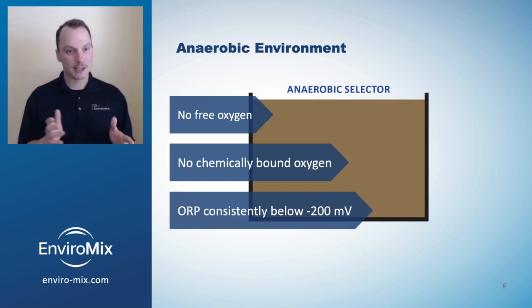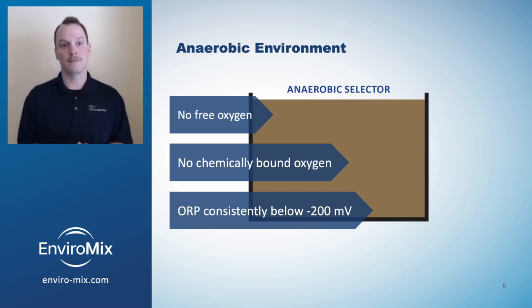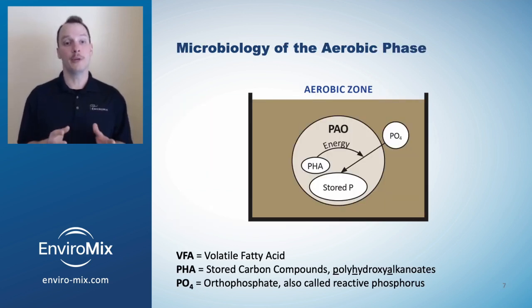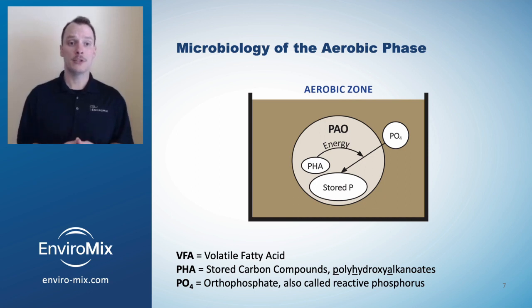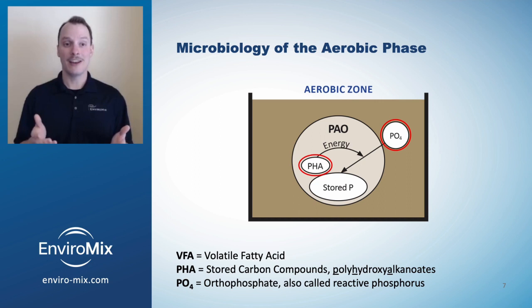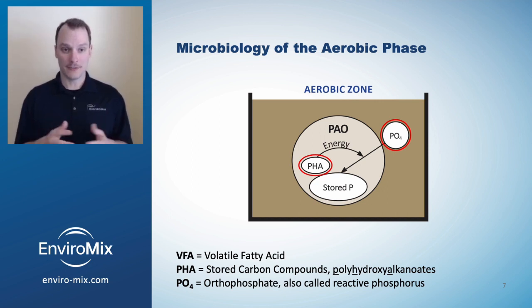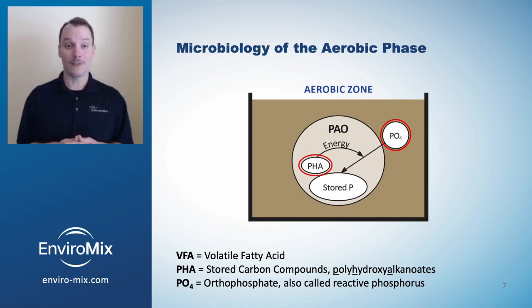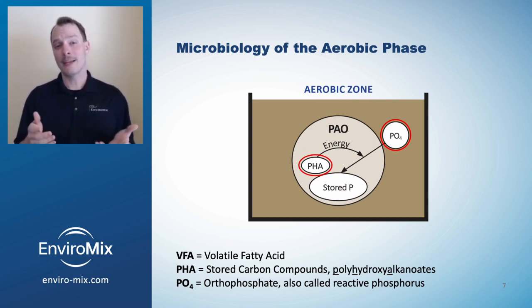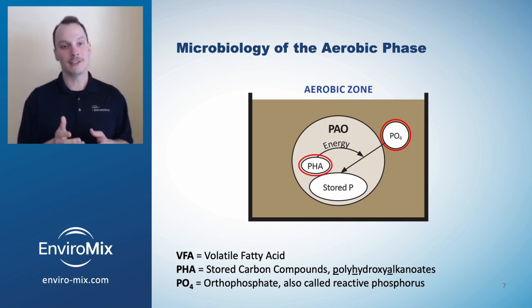After passing through a truly anaerobic selector, the activated sludge enters an aerobic zone. In the aerobic zone, PAOs use their carbon reserves as an energy source for phosphorus uptake and new cell growth. Phosphorus uptake in the aerobic environment is significantly greater than phosphorus release in the anaerobic environment, and that means there's a net removal of soluble phosphorus after the activated sludge passes through this aerobic zone.